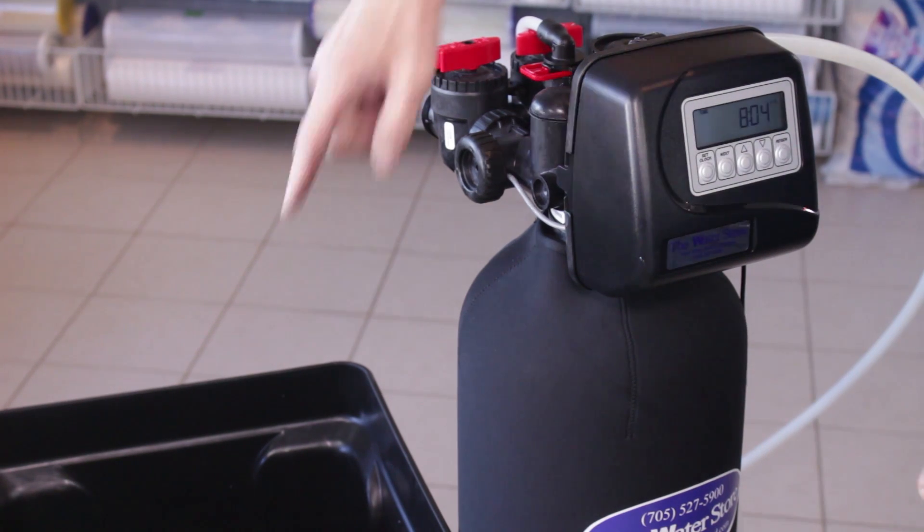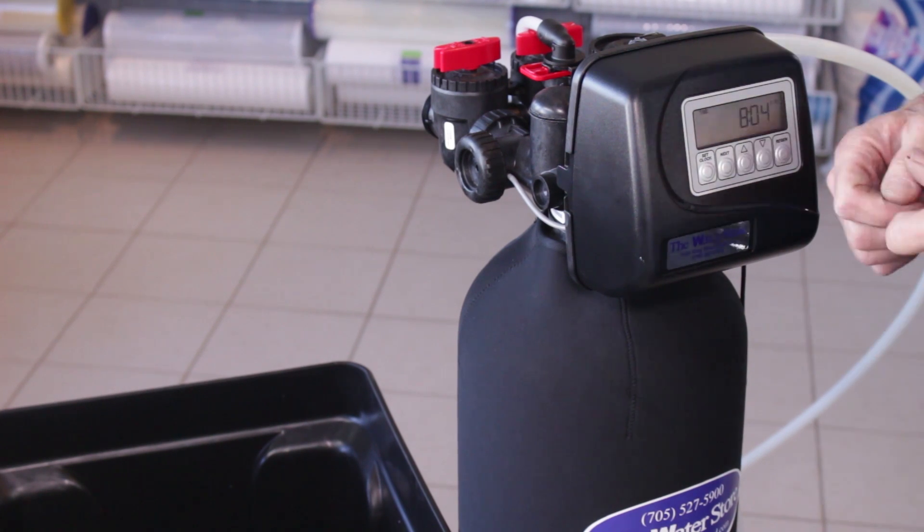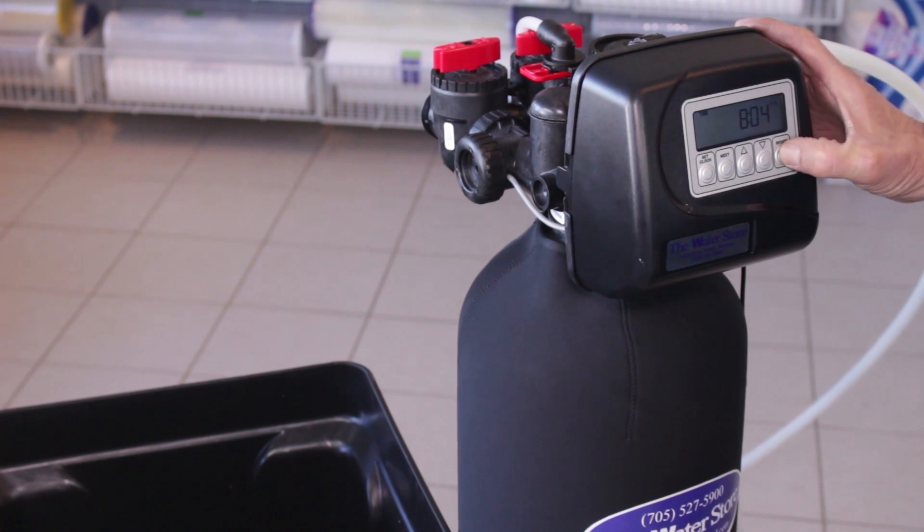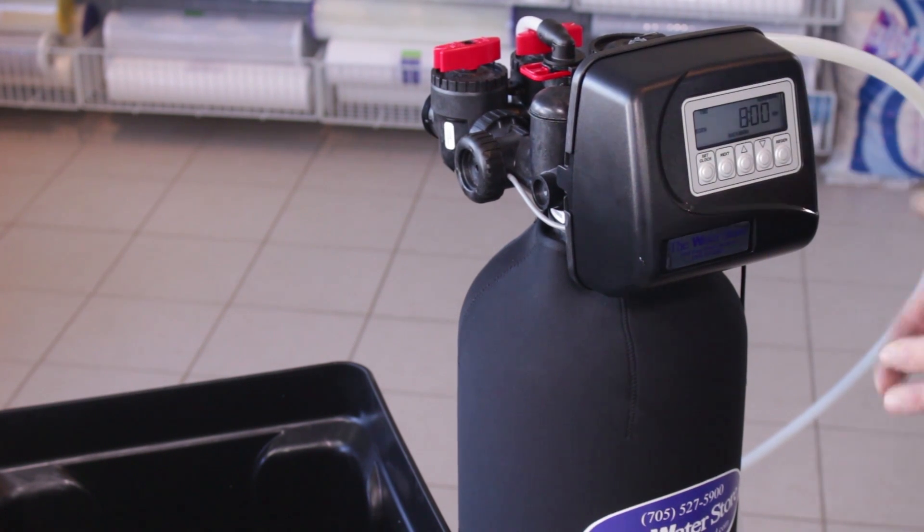Now what we would need to do is add five gallons of water to the brine tank and then we would start to put the unit into backwash. We do that by pushing the regen button and holding it down and usually after about five seconds you can hear the motor start up like now.